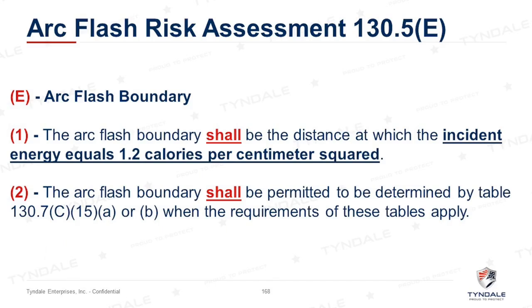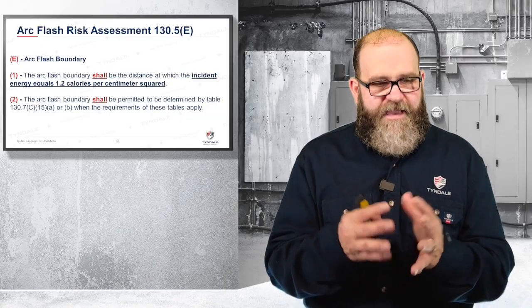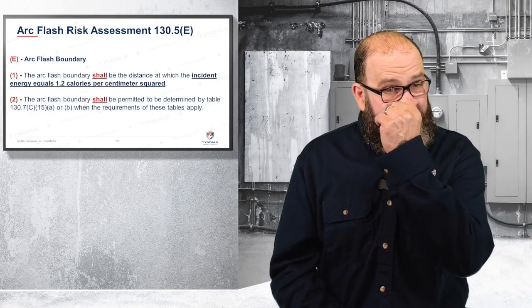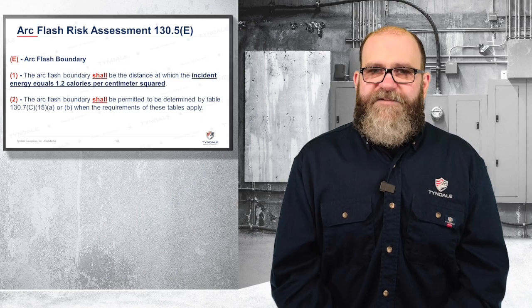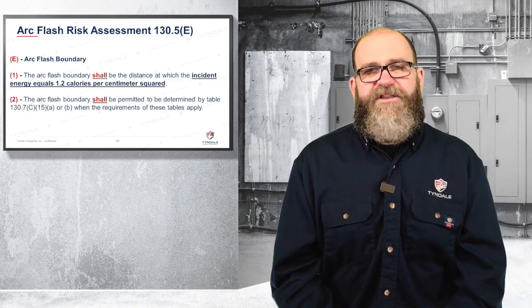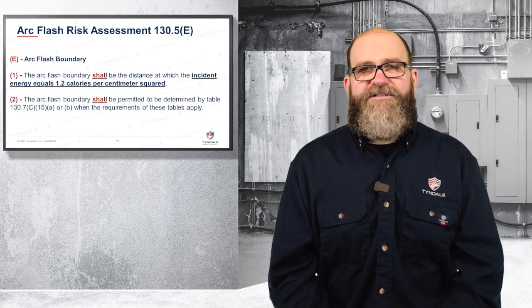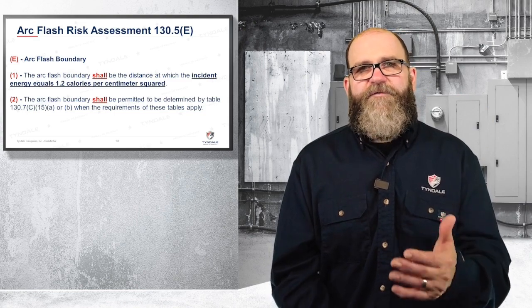Then we get to E, 130.5E, and this talks about the arc flash boundary. The arc flash boundary shall be the distance in which you get a second degree burn. It says the incident energy equals 1.2 calories per centimeter squared. I can't tell you how many times I've heard out in the field, 'Hey, we've got our arc flash boundary set up, and as long as you don't cross that, you're safe.' Well, that's a fallacy. Here's what it says: that you can get those exact burns if you're standing at the arc flash barricade.